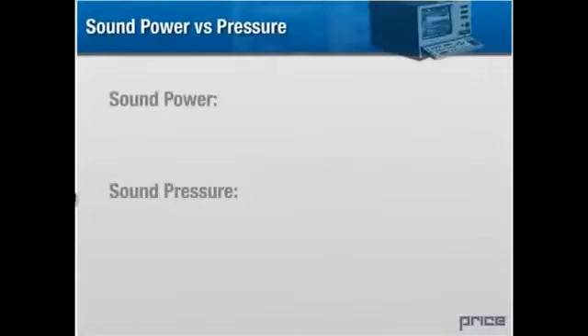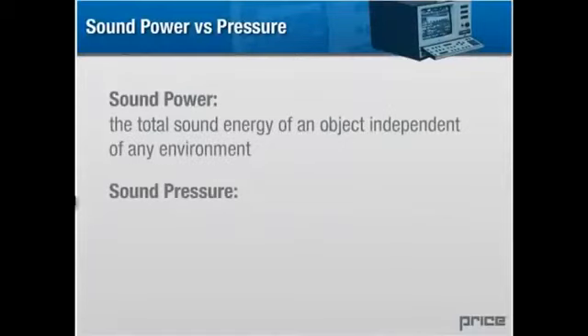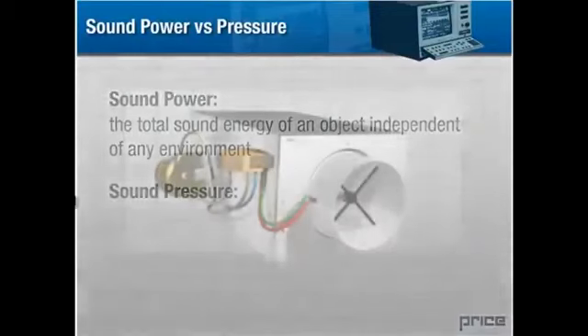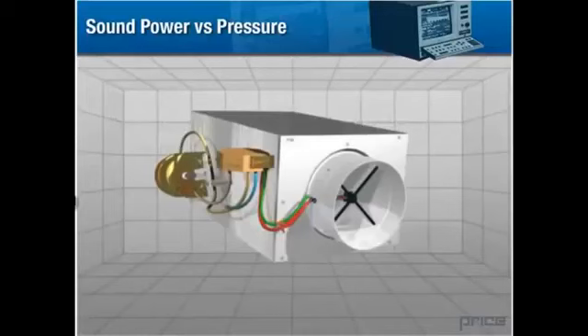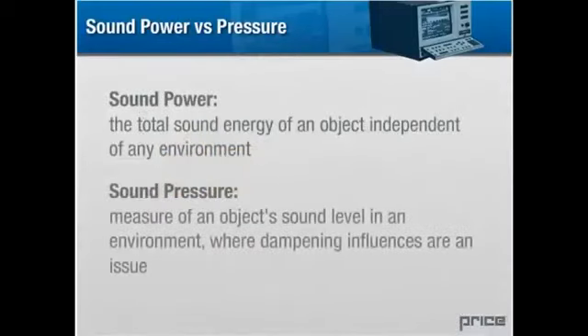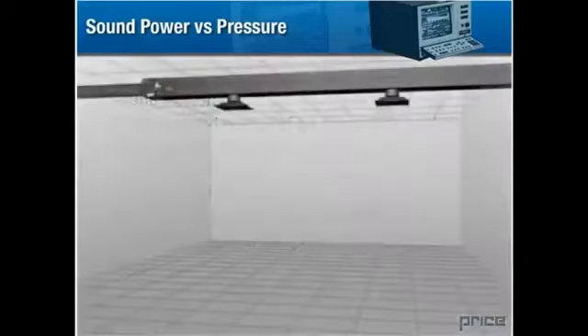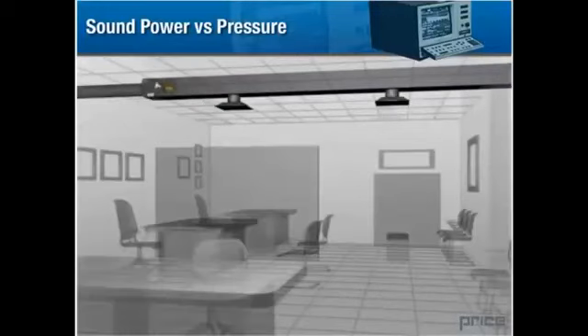Sound power versus sound pressure. It is important to understand the difference between sound power and sound pressure when considering the measurement of an object's sound energy. Sound power is the total sound energy of an object, independent of any environment. We typically determine an object's sound power in a room with no dampening influences. Wherever possible, sound power levels are given for HVAC products to enable reliable side-by-side comparisons. Sound pressure is a measure of an object's sound level in an environment where dampening influences are an issue, such as wall hangings, carpeting, and furniture.